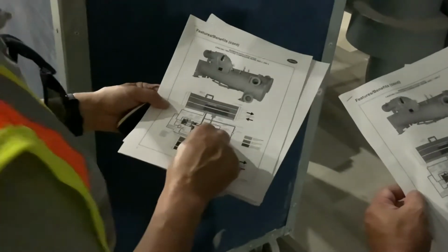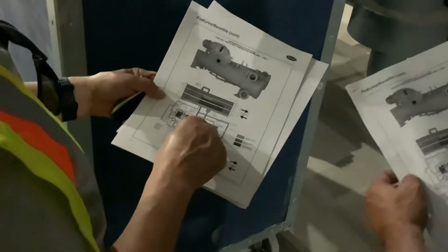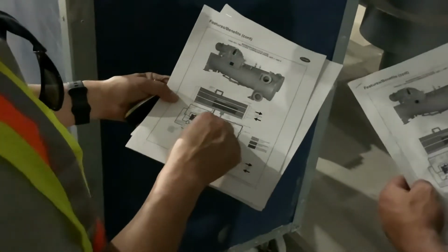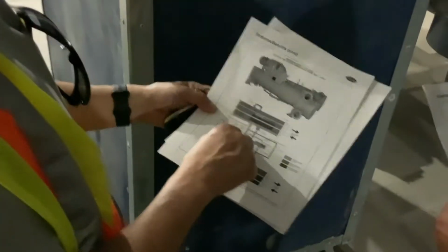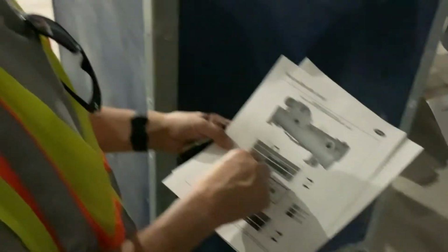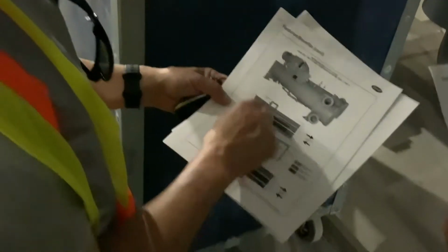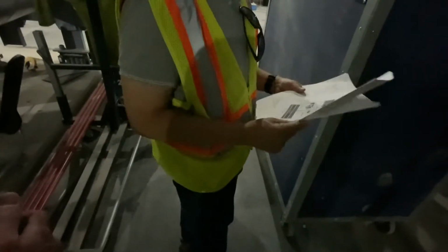And what they're doing is they're siphoning some of the cool refrigerant that's boiled off from your liquid that came out of your condenser, and they're taking that back into the second stage, and that increases your subcooling effect because it cools the refrigerant going into the condenser. Okay. So that's called an interstage economizer. It makes them more efficient. That's going to cost some extra.